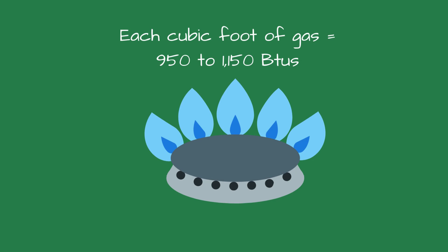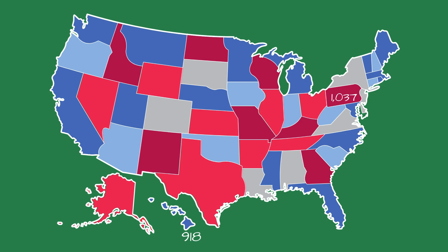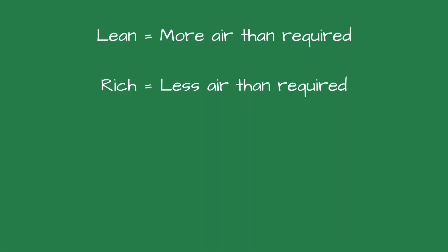If you are a flame watcher like me, you may notice what looks like sparklers at the tips of the flame — this could indicate lower BTU content. The BTU content also varies from state to state. Pennsylvania's average BTU content per cubic foot of gas is 1,037 BTUs, while Hawaii's average is 918 BTUs. Most experts use 1,000 BTUs per cubic foot as the industry standard. When more air is supplied than required, it's called lean, and when less air is supplied than required, the flame is referred to as rich.